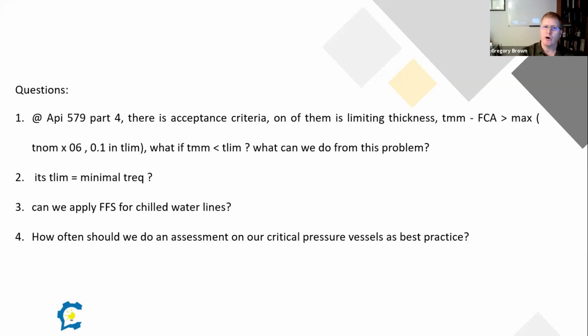Most of the damage was occurring very early in the cooling process. So what they did was start cooling the vessel slowly at first, bring it down to a little bit lower temperature, and then use the full cold chilled water to do that. So absolutely, yes, you can apply that.